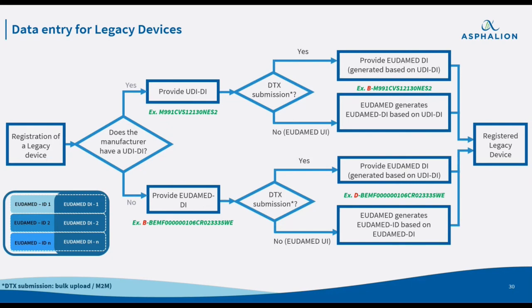Considering that we have a legacy device already bearing a UDI, the next step for the registration is to provide that UDI. So as legacy devices have had their own identifiers, once we have the UDI, we will need to create the fake basic UDI, the so-called EUDAMED DI. So how can we do it? Well, that depends on the type of data submission we are carrying out.